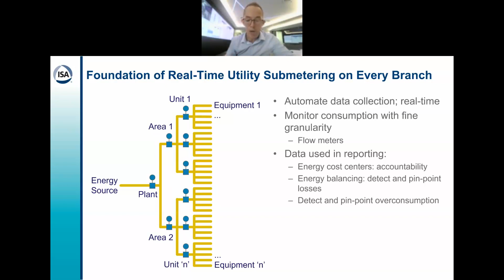So sub-metering of every branch is key to all energy management software functions like the cost centers, the precision with which overconsumption is pinpointed, the granularity of reports and dashboards, and the precision of leak detection. All are determined by the level of sub-metering you're doing. That is, sub-metering is a key success factor for energy management. So don't overlook sub-metering. And other measurements required for energy management include pressure and temperature to calculate the enthalpy of steam, and other measurements for calorific value of fuel.